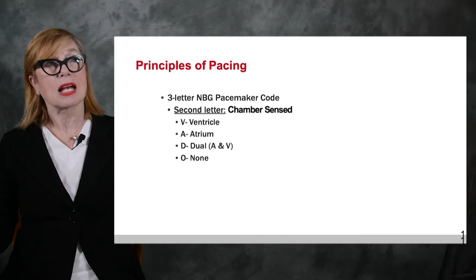Okay, well that's pretty good, but you always have to wonder if it says no chamber is being paced, that's kind of a strange thing, and we never actually have that when we talk about a pacemaker. The next thing is what chambers are sensed. So again, the same. Ventricular chamber, V, atrial chamber, A, and D, dual chamber, and O, none. Now we do often have pacemakers that are D for pacing and O for sensing, meaning that we have a pacemaker that is not sensitive to the patient's own endogenous rhythm.